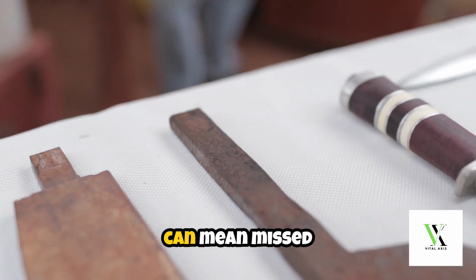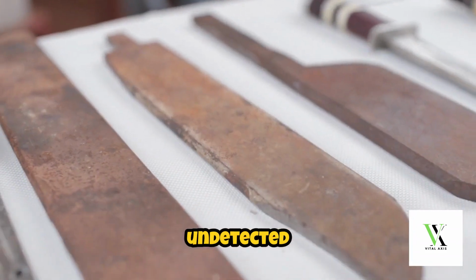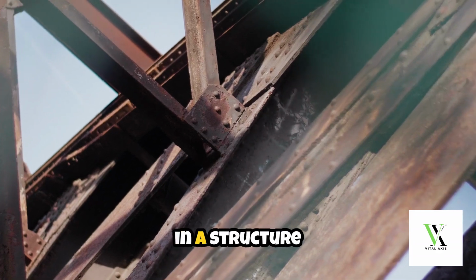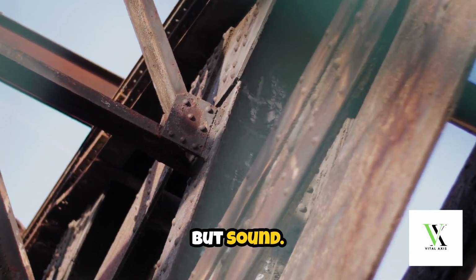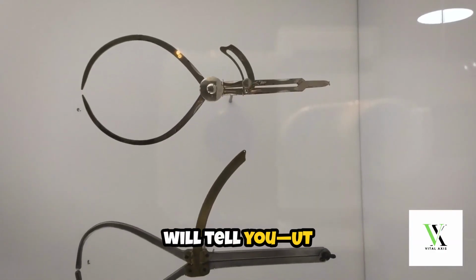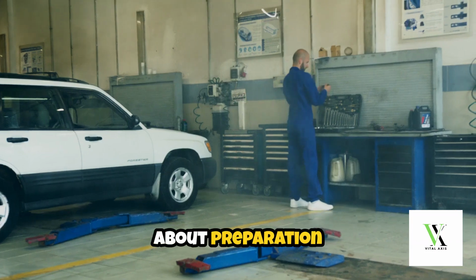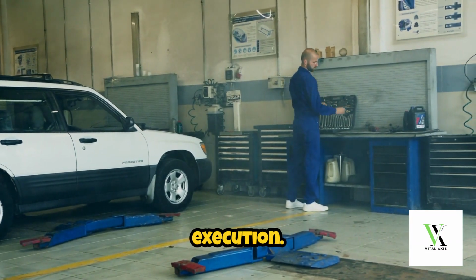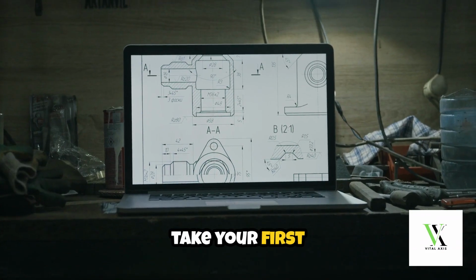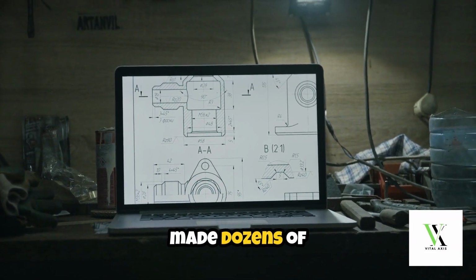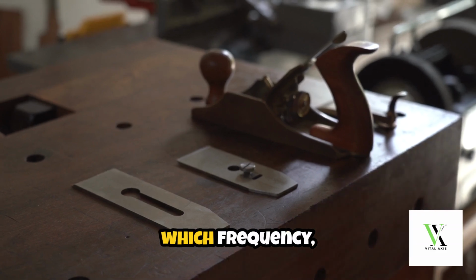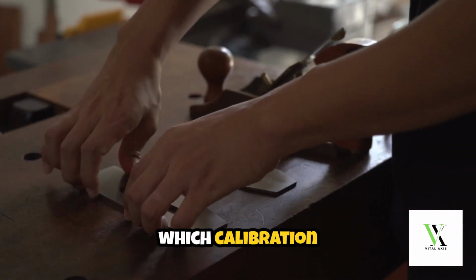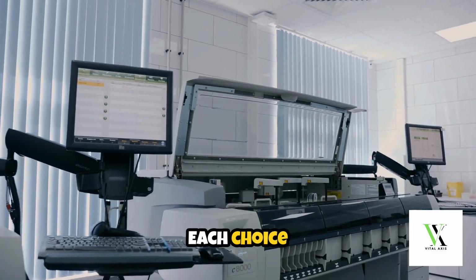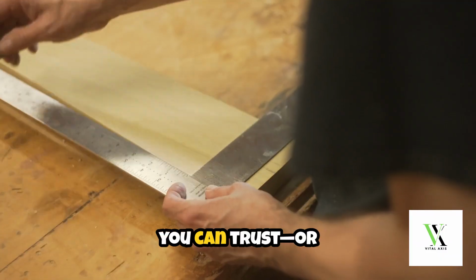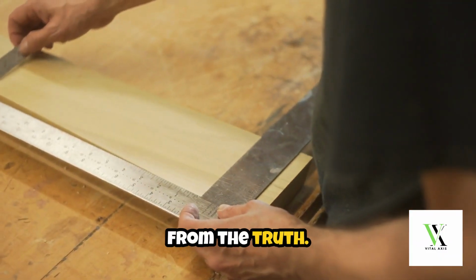The wrong tool can mean missed corrosion, undetected cracks, or false confidence in a structure that's anything but sound. Every seasoned inspector will tell you, UT is as much about preparation as it is about execution. Before you take your first reading, you've already made dozens of decisions: which probe, which frequency, which gauge, which calibration block. Each choice brings you closer to a result you can trust or further away from the truth.